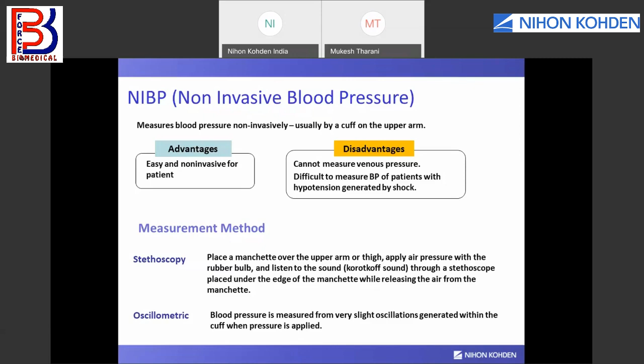So what are the measurement methods for NIBP? There are two methods. One is the stethoscopy method, which is a manual method of measuring the blood pressure by listening to the Korotkoff sounds. The second method is the oscillometric method, which is measured by machines. Here a machine is measuring the oscillations which are generated within the cuff. So we'll talk about these two methods now.